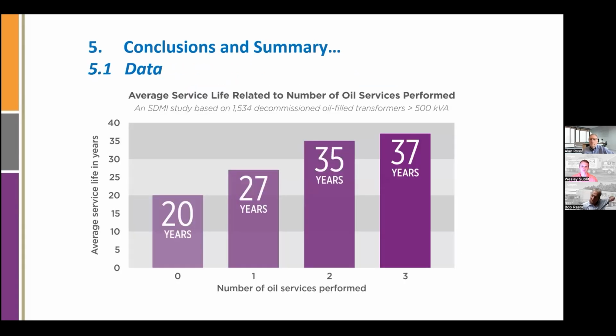We did a study a number of years ago. It was presented in a CIGRE and IEEE paper, where there were 1,500 transformers in our database that were decommissioned. It showed the effectiveness of service work in the in-service range, perhaps prompted by trending data showing that it's for real, you've got a situation brewing, so go ahead and perform the service.